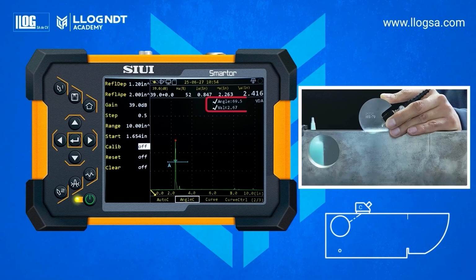In the upper right corner, the corrected angle will be displayed, as well as the K value, which corresponds to the tangent of the angle. The permitted tolerance is plus or minus 2 degrees, as established by the AWS D1.1 code. It is important to enter the hole values, depth, and diameter, according to the transducer position.